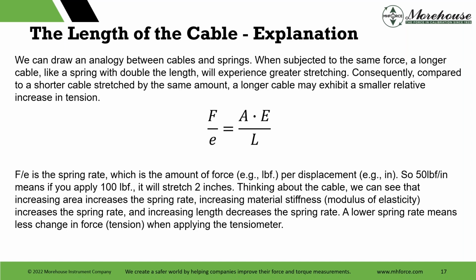Really, I mean, the cable length is going to be impacted here, of course. But if you think about the cable, we can see that increasing the area increases the spring rate, increasing material stiffness, modulus of elasticity, increases the spring rate, and the length decreases the spring rate. A lower spring rate means less change in force when applying the tensiometer. If you think about it, just a rubber band, and how a thinner or longer one will stretch more than its thicker or shorter counterpart. Cable is going to act the same way.